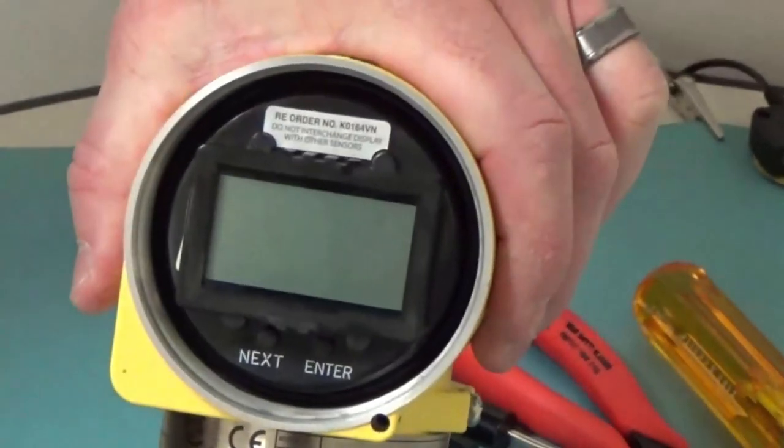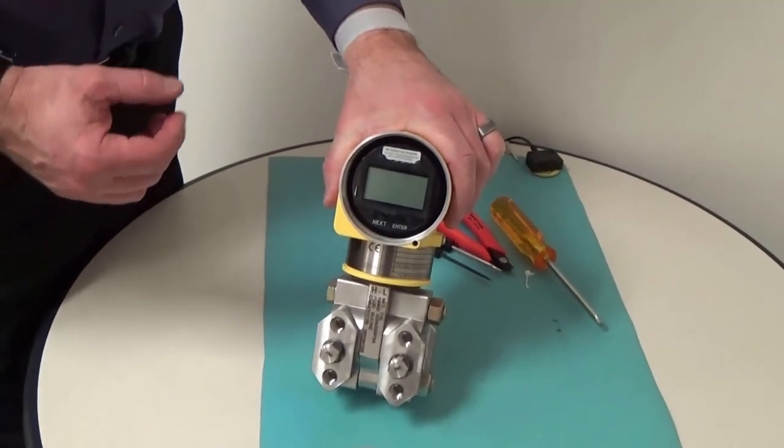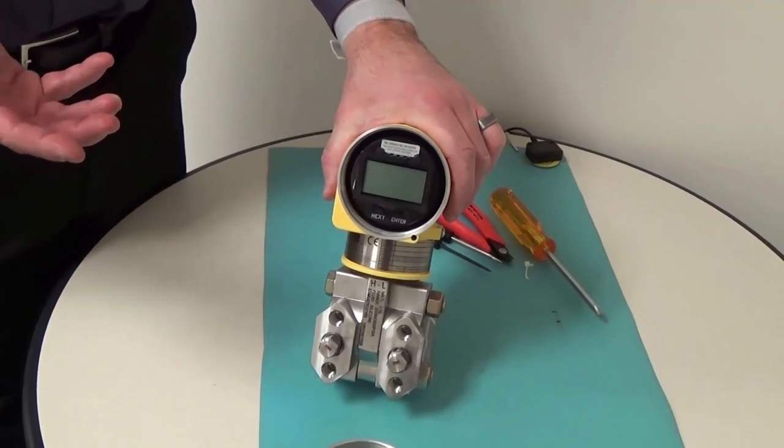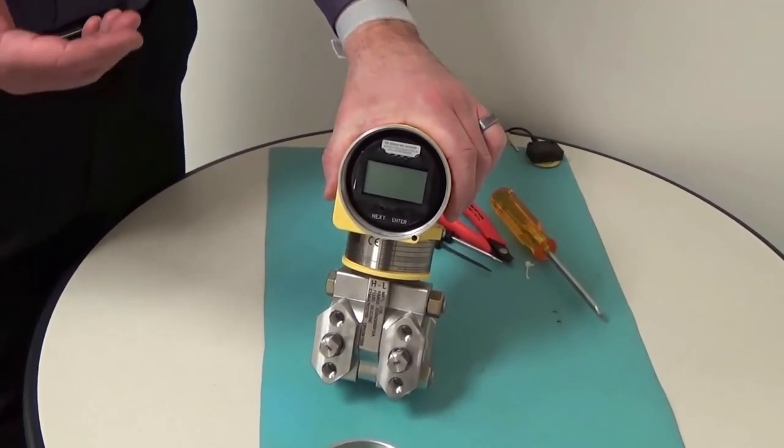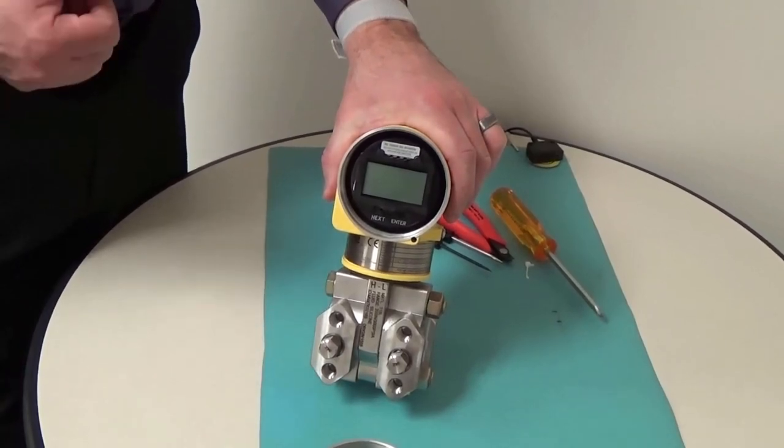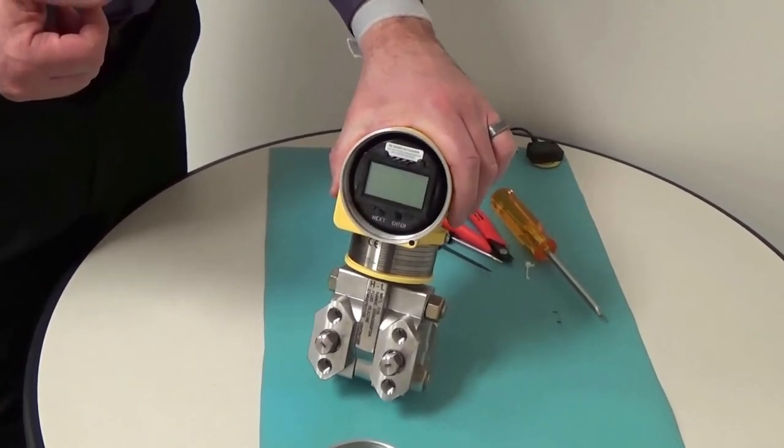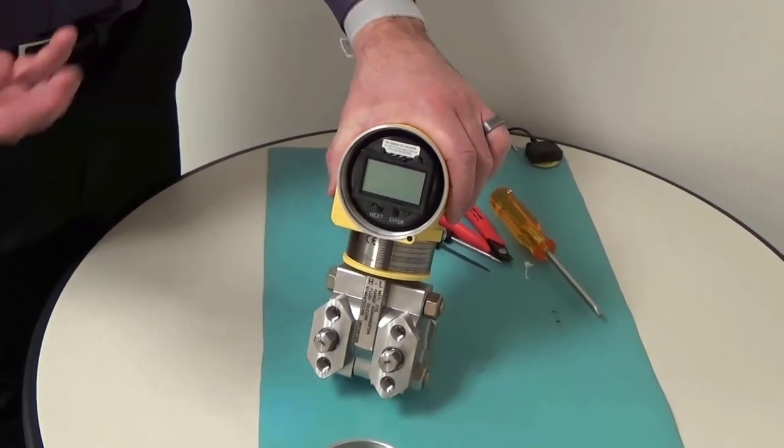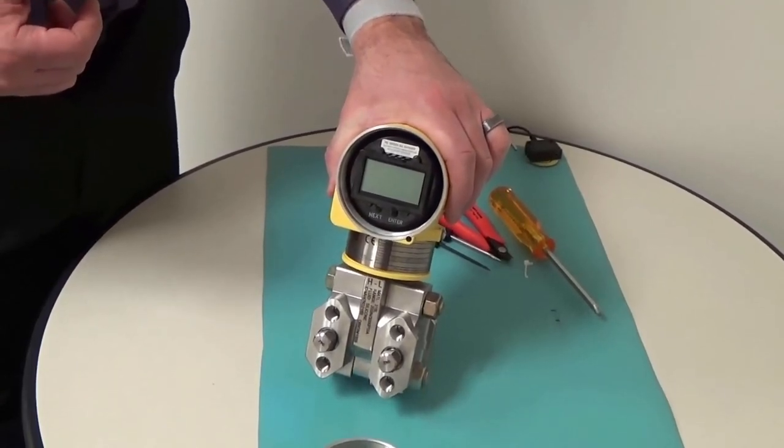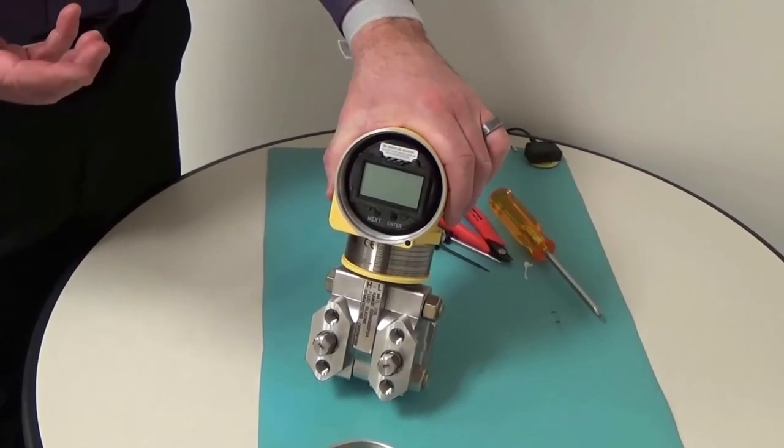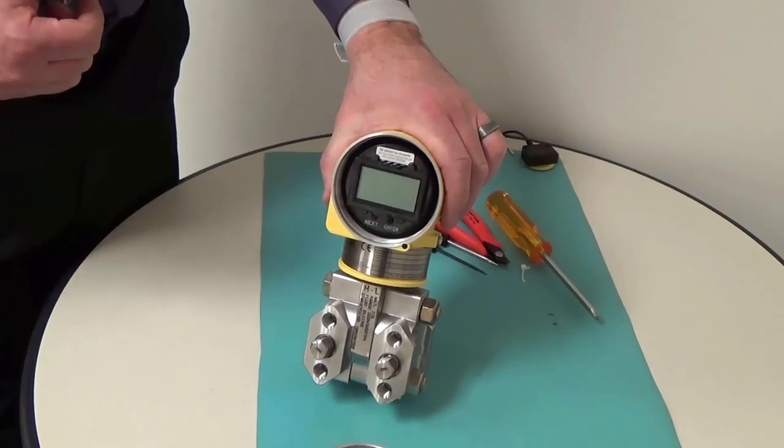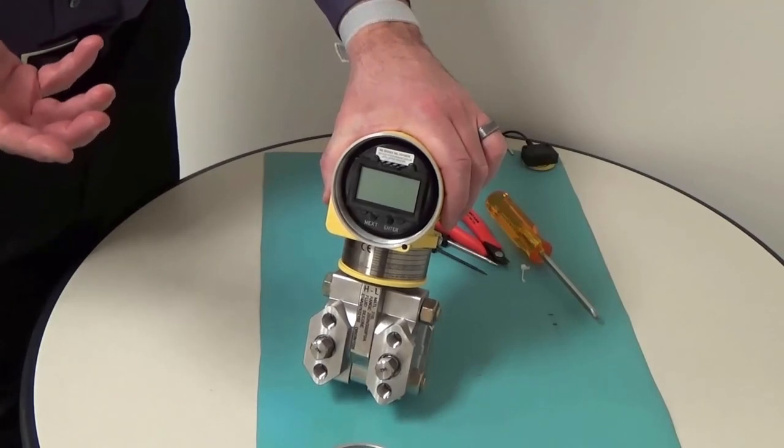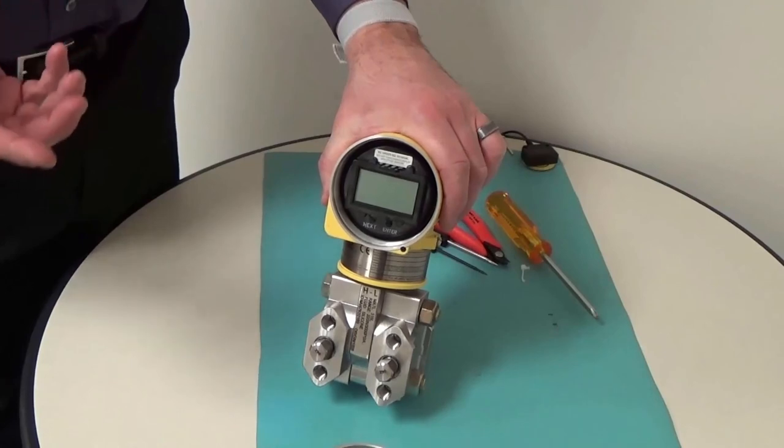One of the things to be aware of in regard to the battery is that it is feasible to set up a register assignment so that you can monitor in software the battery voltage or monitor the battery voltage through the host and set up alarms on it. The battery voltage shows up in the register as a value which is 1000 times the actual voltage. For instance these batteries are 3.6 volt batteries, so you'll see a new battery show up as a value of 3700. If that value gets down to let's say 3000 which is 3 volts, that's an indication that the battery needs to be changed.